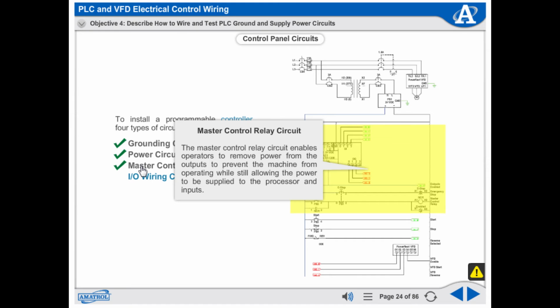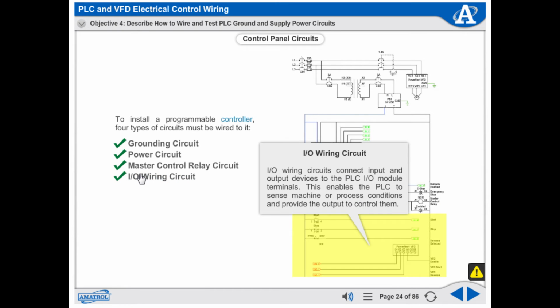The master control relay circuit enables operators to remove power from the outputs to prevent the machine from operating while still allowing the power to be supplied to the processor and inputs. I/O wiring circuits connect input and output devices to the PLC I/O module terminals. This enables the PLC to sense machine or process conditions and provide the output to control them.